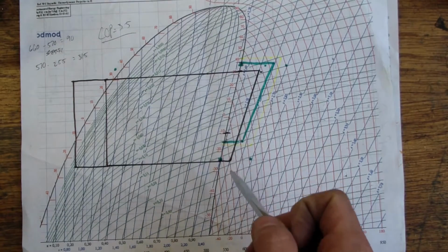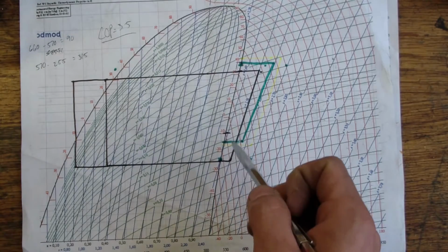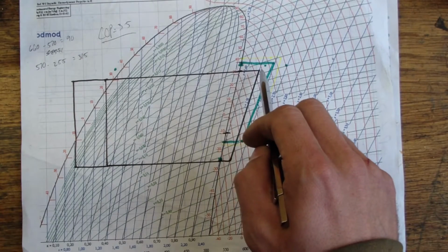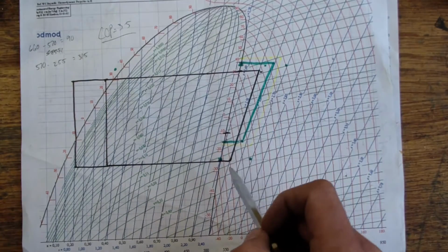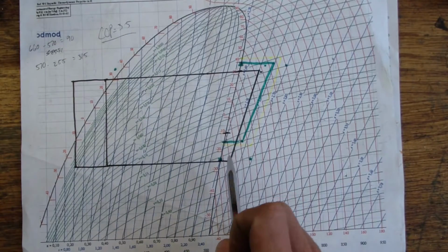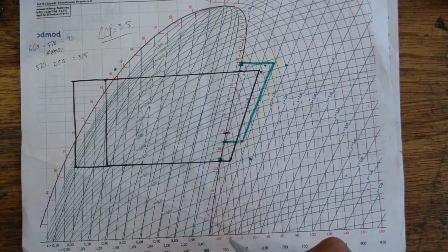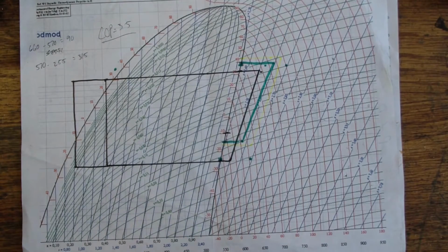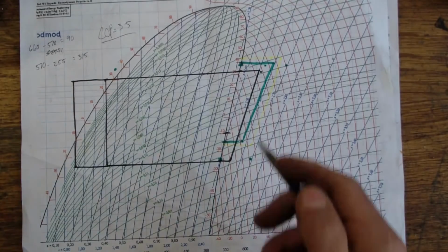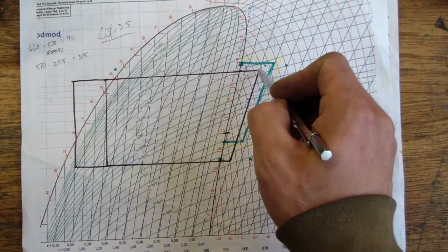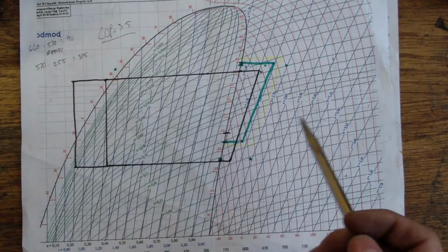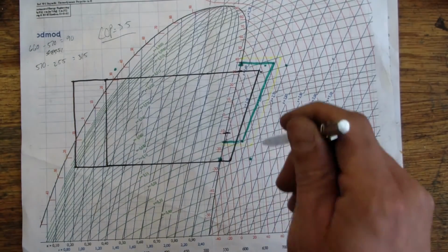Our suction temperature in this case is about negative 10 degrees Celsius. And by the exit, we're somewhere up here between 50 and 60 degrees Celsius. We'll call it 55. So we've crossed several isothermal lines. We've traveled almost perfectly along the lines of constant entropy, or the isentropic line. That doesn't normally exist in the real world, but that's the way I charted it. My actual superheat value is probably a little bit higher, which would put it a little bit to the right of the line of constant entropy, meaning it's not reversible. And I know it's not reversible because, well, that doesn't really exist.